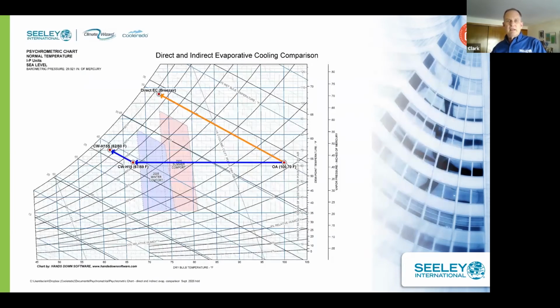Now, the key thing to understand our units is to talk about psychrometrics. If we look at an outdoor air condition of 100 degrees, 70 degrees wet bulb, direct evaporative cooling, or adiabatic cooling, goes up this line, and you're really not doing any work on the air. Our Climate Wizard units are indirect evaporative cooling and start from that 100 degree outdoor design condition and go to the left. So this is purely sensible cooling and achieving energy savings of up to 80 or 90%.